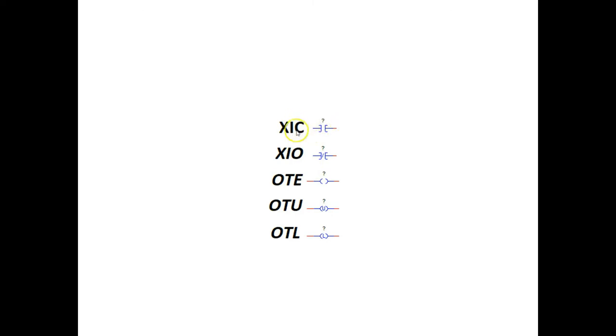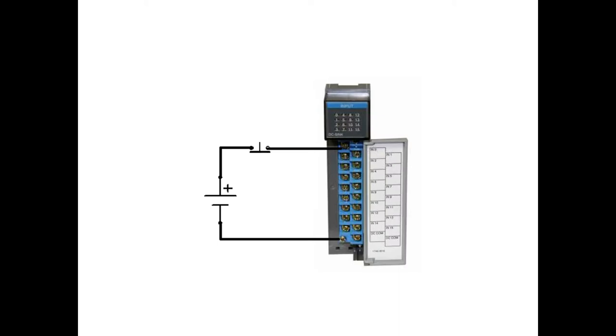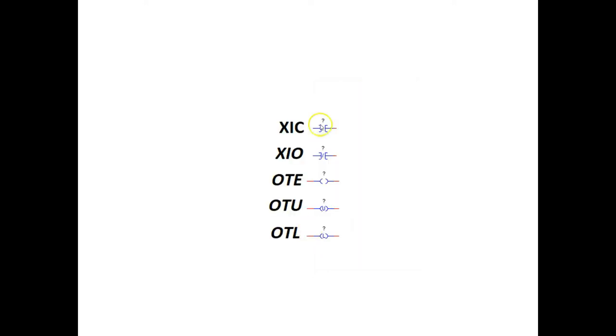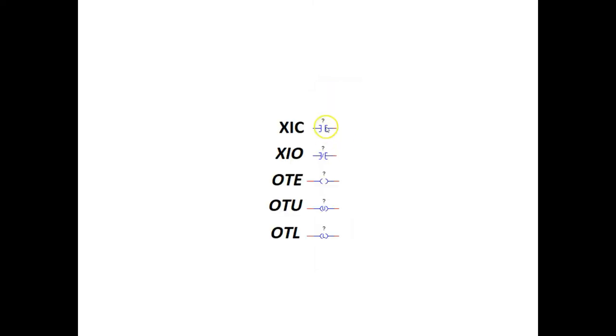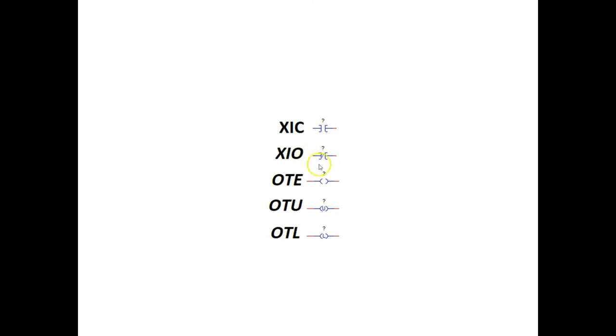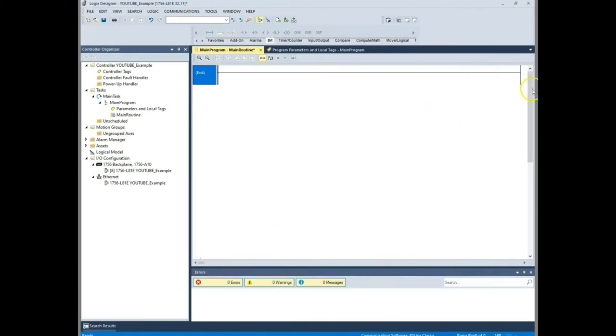Why would Allen Bradley call this XIO and XIC? Well it's because what you have to understand is that it's looking at your input card. So if we have a XIC for instance, remember your XIC would be like a normally open contact. But if you have an XIC that's looking at input zero here and I've got a normally closed switch that's connected to my power supply, well I'm allowing 24 volts or power or a high on this input zero all the time. In that case this would be closed or enabled. And that's what that's saying. It's saying if your input is closed, you're going to enable this. Examined if closed. The same is true with the XIO where if you had a normally open contact and it had a zero on your channel that this is looking at, then this would be enabled because it works like a normally closed contact. And so that's the reason that Allen Bradley calls these XICs and XIOs.